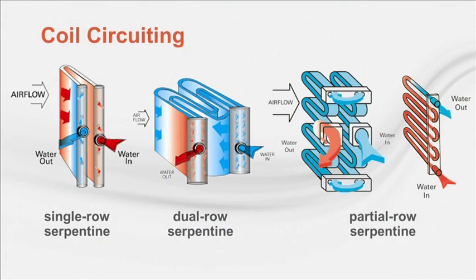Partial row serpentine circuiting, also known as fractional circuiting, feeds only some of the tubes in the coil row, which allows for increased water velocity. This design is typically used more for heating coils. Changing the circuiting can drastically change water velocity and heat transfer characteristics. Tailoring the coil geometry to achieve a desired water velocity can help minimize the negative impacts of either too high or too low velocity.